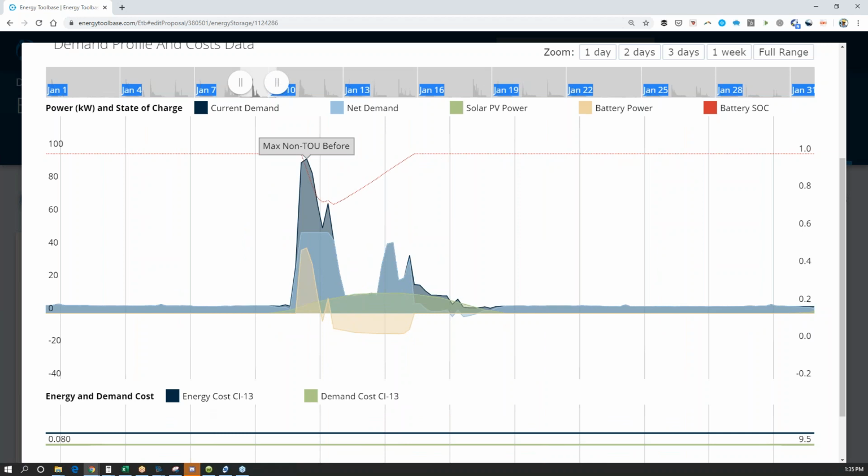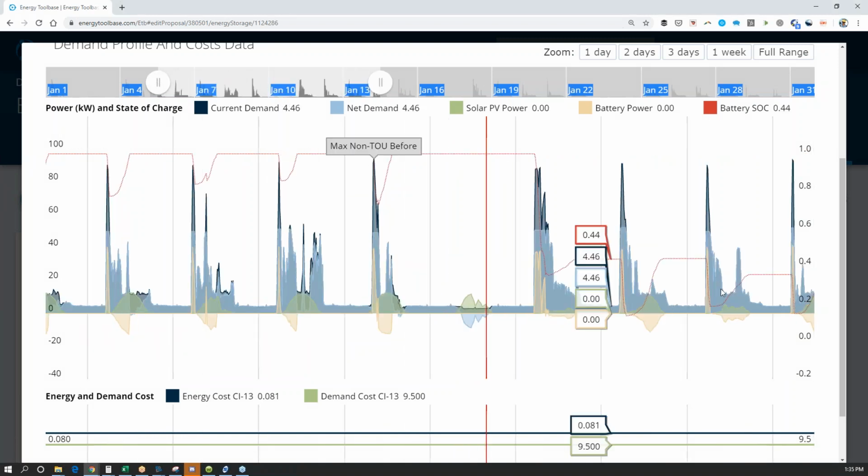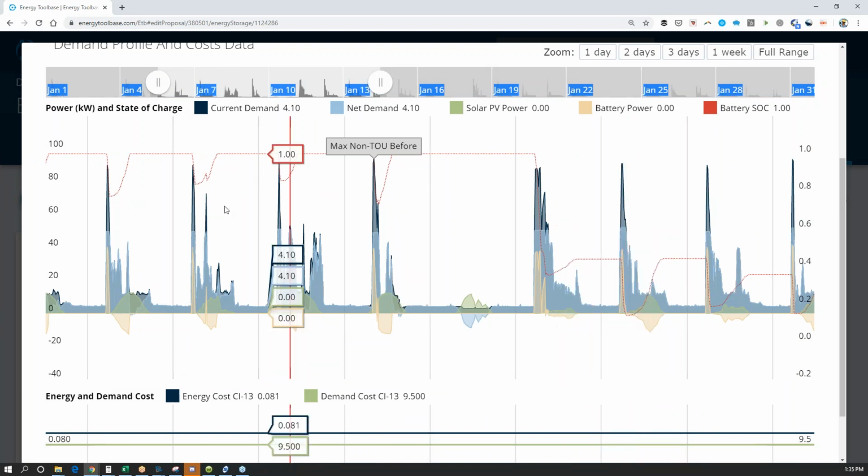And what does this tell us based on what we know? Is this going to be a good size or not? Well, in this red line, we have the battery state of charge. And I don't really know how it scales on this scale. Maybe the scale's over here at 100% and 0 would be fully discharged. But we look at how it is compared to its neighbors. And so now it's going down to a full state of discharge at this point.